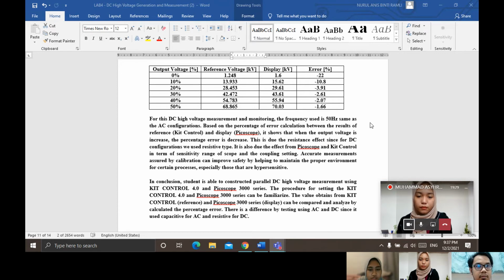This is due to the resistance effect, since for DC configuration we use the resistive type. It is also due to the effect from picoscope and kit control in terms of the sensitivity range of the scope and the coupling setting. Accurate measurement assured by calibration can improve safety by helping to maintain the proper environment for certain processes, especially those that are hypersensitive.